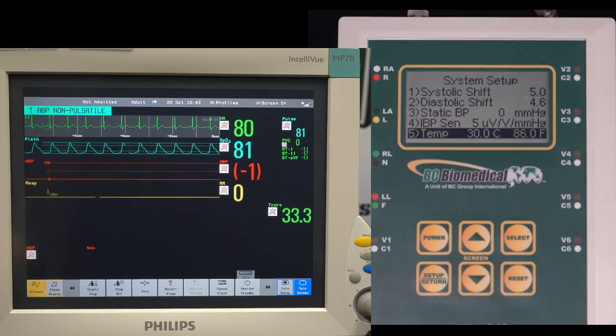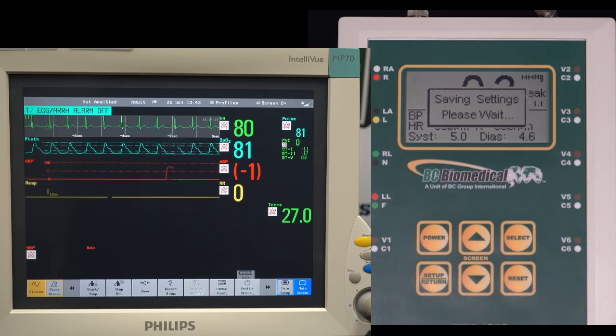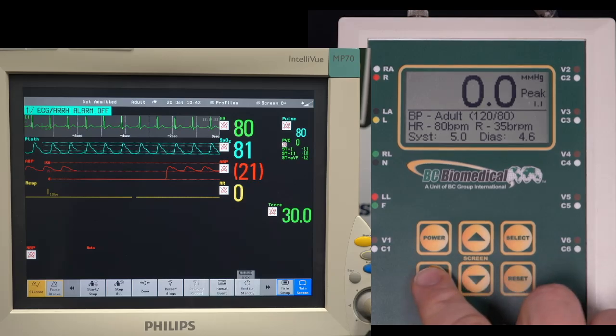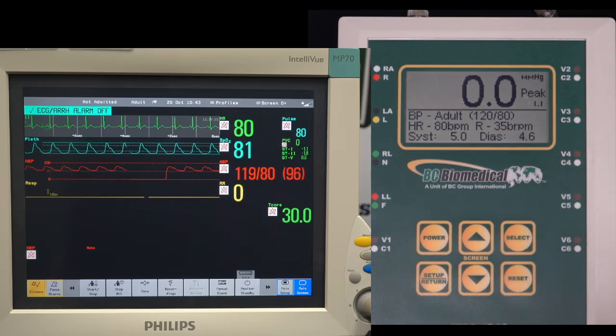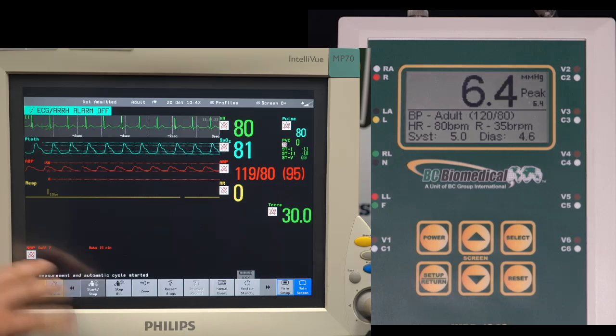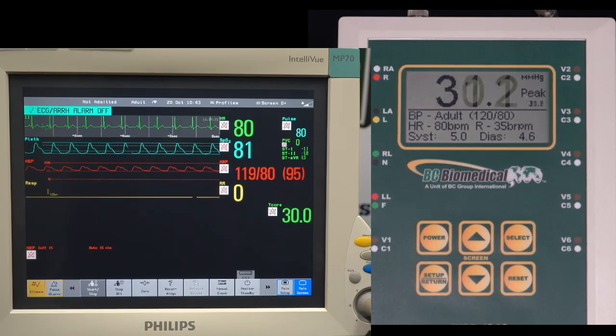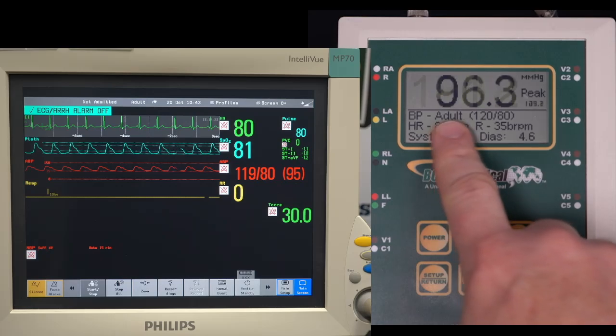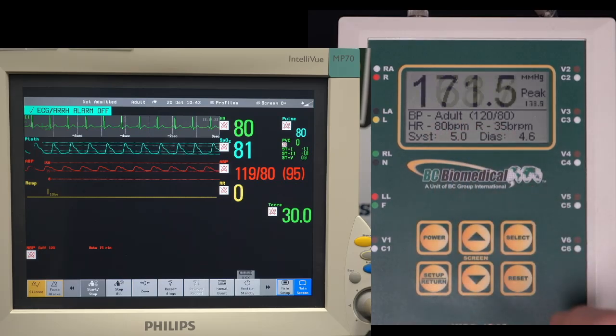And we can see that when I hit enter, now we can see that update here on the monitor. Okay, so that's those simulations. Now, in order to run the NIBP, I'll go ahead and run that. It's going to run in the background, and it's inflating the cuff. We can see the pressure displayed on the screen here.